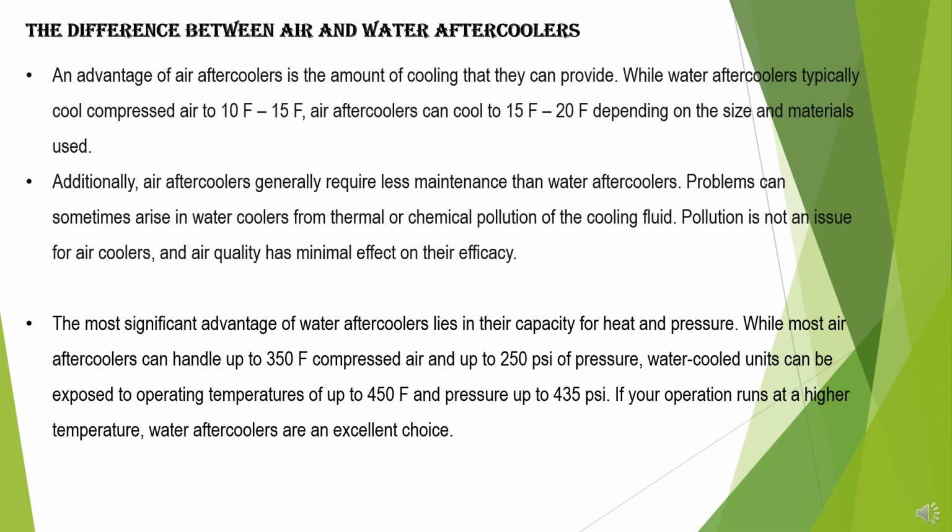Problems can sometimes arise in water coolers from thermal or chemical pollution of the cooling fluid. Pollution is not an issue for air aftercoolers, and air quality has minimal effect on their efficiency. The most significant advantage of water aftercoolers lies in their capacity for heat and pressure. While most air aftercoolers can handle up to 350 Fahrenheit compressed air and up to 250 psi of pressure, water-cooled units can be exposed to operating temperatures of up to 450 Fahrenheit and pressure up to 435 psi.